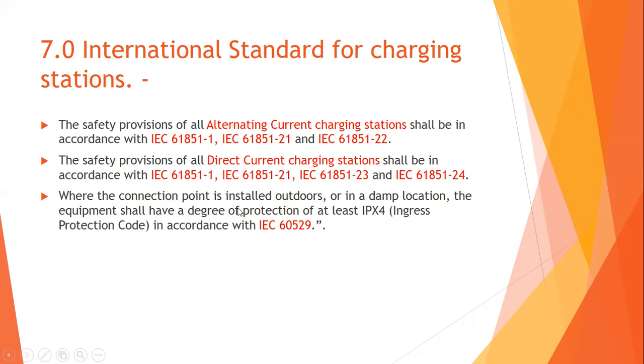Where the connection point is installed outdoors, in a damp location, or near a damp location, the equipment shall have a degree of protection of at least IPX4, in accordance with IEC 60529. These are the latest guidelines of CEA covering all seven rules of Chapter 11 on safety provisions for electric vehicle charging stations.